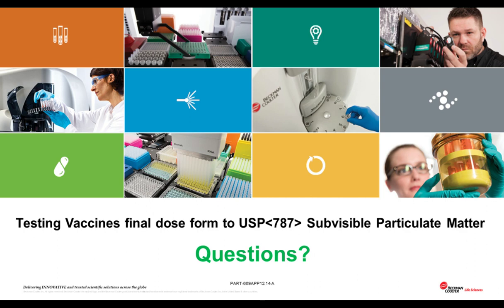Please explain again what tare volume is. Yes, certainly I will. So the tare volume is the volume of the sample pathway that the sample has to pass through up the sample probe, leading to the light obscuration counting window where the particles are counted. And in many general purpose counters, this tare volume is quite large. So it prevents the test being achieved with a small volume of sample.